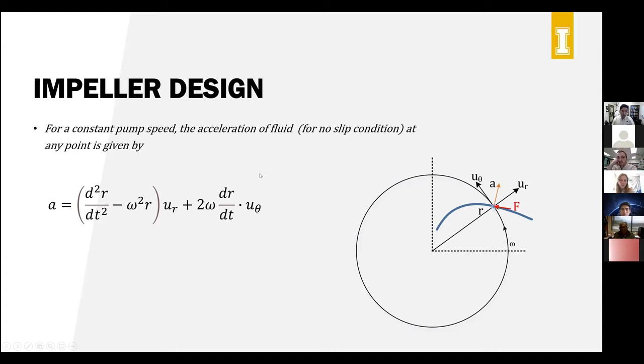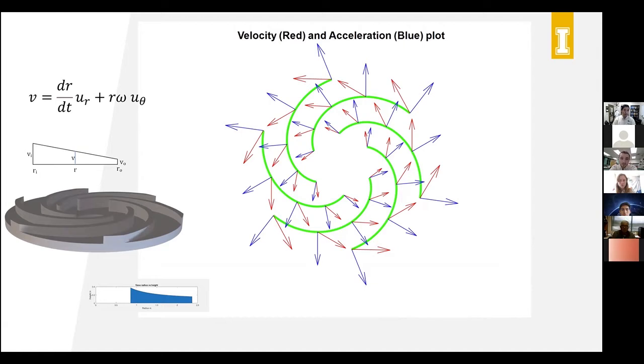And we looked at this for a constant speed vane that is rotating at some angular speed of omega. And we also assume that there is no slip between the fluid and the vane itself for the most efficient pump. That means the fluid is rotating at the same angular velocity as the vane. Right. So of course, that acceleration is a function of velocity. And there are, again, 2 components of velocity. One is the tangential velocity, which at any given radius is proportional to the speed of this vane. And then there is a radial velocity, which depends on the impeller profile and some other factors.